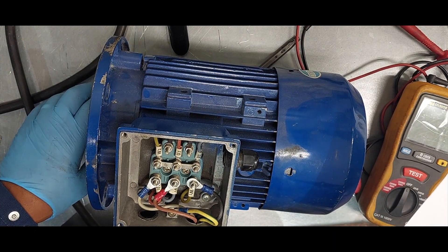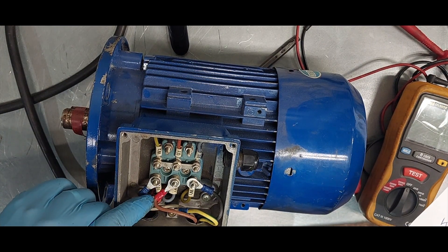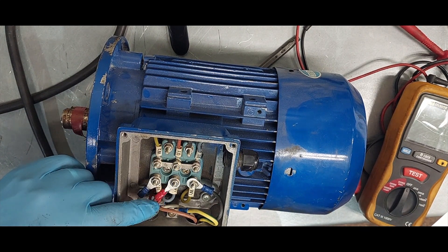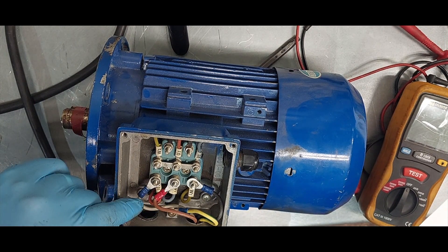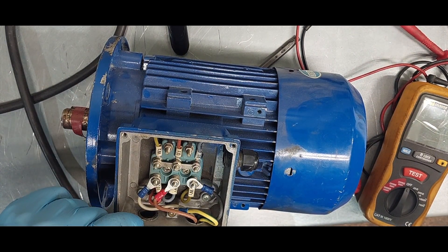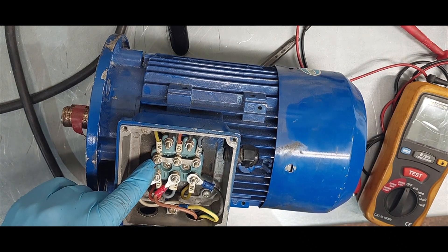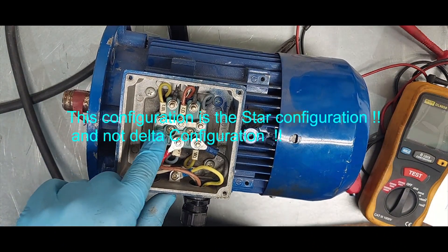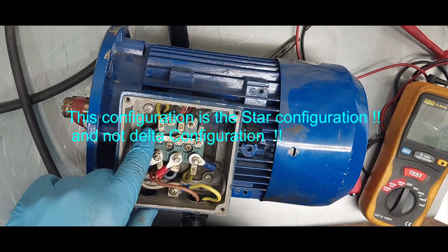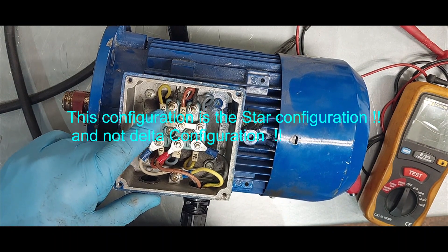We'll be looking for low resistance in the windings of the motor. We connect U1 and U2 to measure the resistance between them, then do V1 and V2, and check W1 and W2. In order to check these parameters properly, since this motor is connected in star, we have to remove the star connection so that we can check the individual windings.